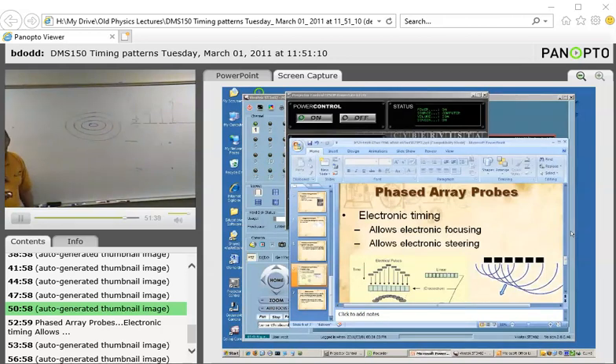Okay? That was the good thing about it, is that an annular array transducer had the ability to focus in the lateral and the elevational plane simultaneously. Okay, so when we were in the labs and we were playing with lateral resolution, and the next week we looked at elevational resolution, we saw that they didn't always correlate. In fact, you could adjust the lateral resolution with our new transducers, but you never could adjust the elevational plane resolution, except for that one probe, which didn't actually work very well anyhow.